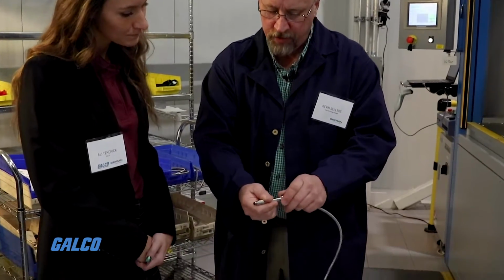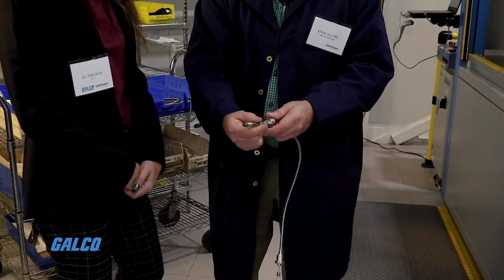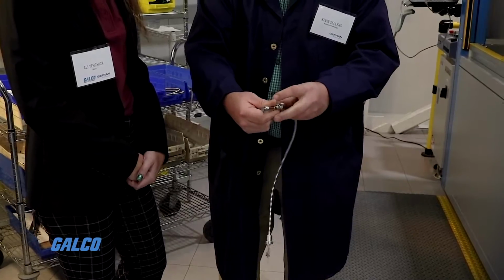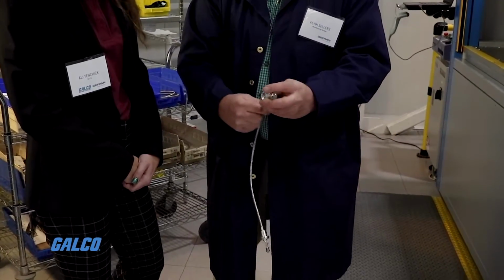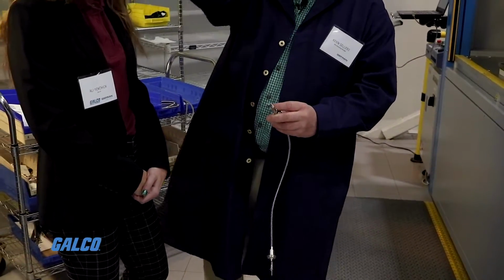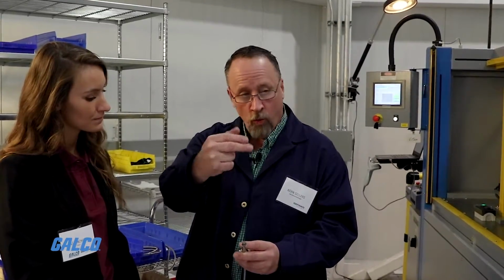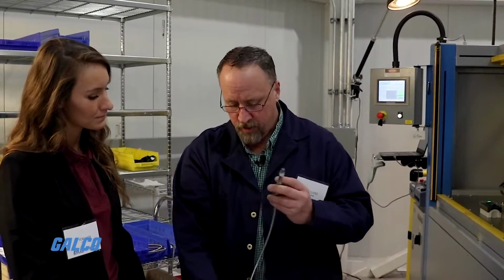Once this is done, they'll do a secondary weld on this, which we call a hot weld, and another weld here we call a thermocouple weld. Once this is all welded up, this sensor can go into the fill room, be filled with the media, whether it be oil or mercury. When it comes out the next morning, this sensor is ready to be calibrated.